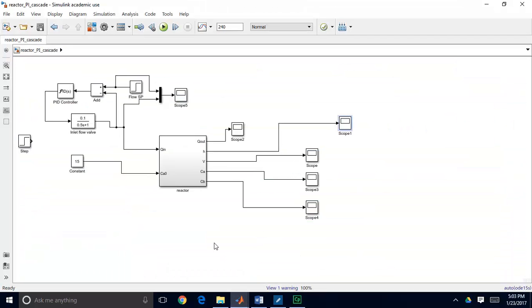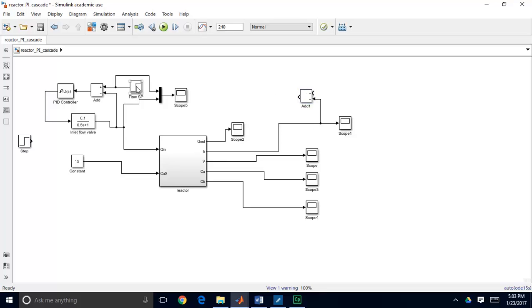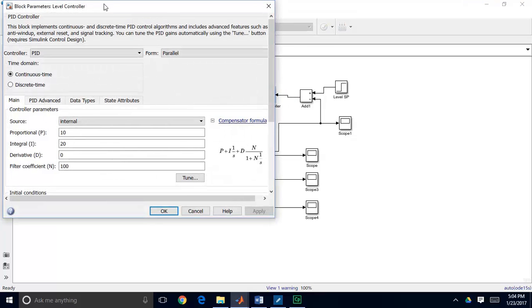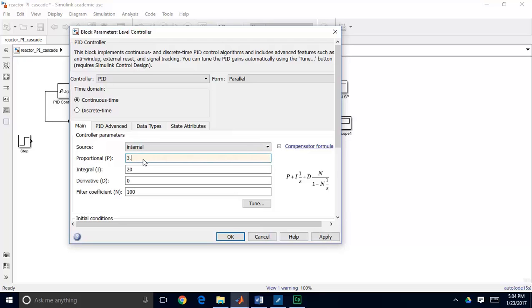Going back to the Simulink model, I'm going to copy and paste the summation block and connect it — this is equivalent to measuring the tank height. I'll also copy the set point block, and now this becomes my level set point. I'll add in a PID controller and call it my level controller. Because I copied it from the flow controller, it will have those old tuning parameters, so I'll double-click and change the tuning parameters to P equals 3.3 and I equals 0.2.